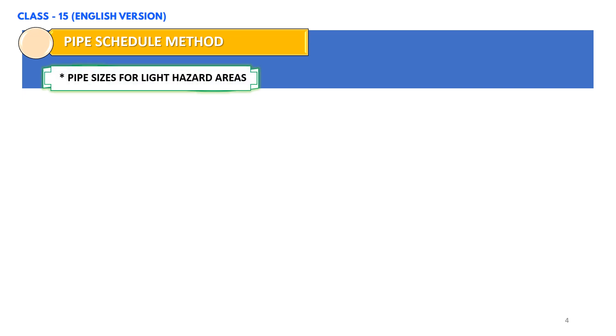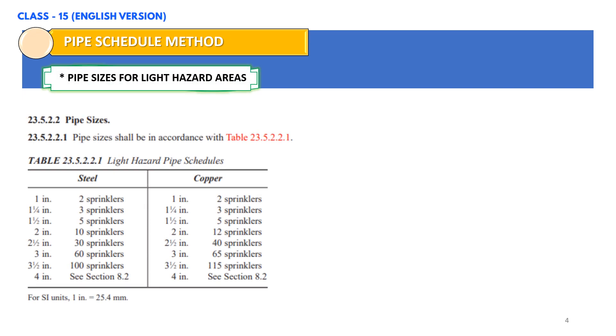Pipe sizes for light hazard areas. As per NFPA 13, pipe sizes shall be in accordance with the table as shown on your screen. For steel pipes: if we have two sprinklers, we can use one-inch pipe; for three sprinklers, we can use one and one-quarter inch pipe (32 mm); for up to five sprinklers, we can consider 40 mm (one and a half inch) pipe; and for 10 sprinklers, we can use two-inch pipe.